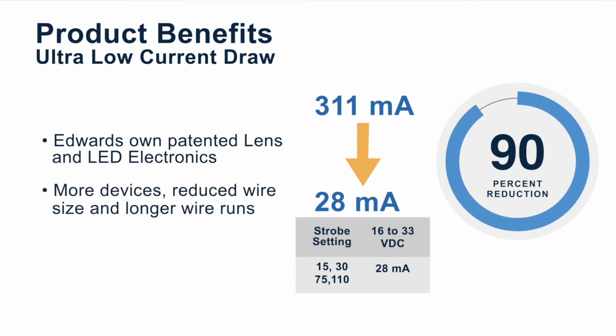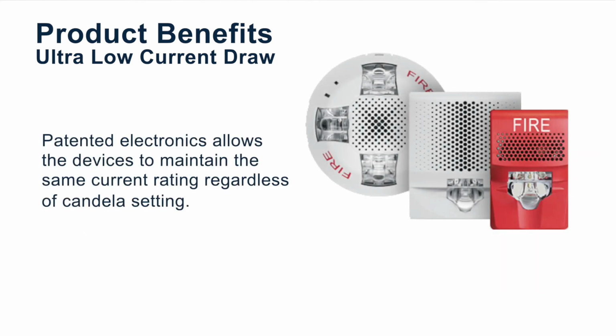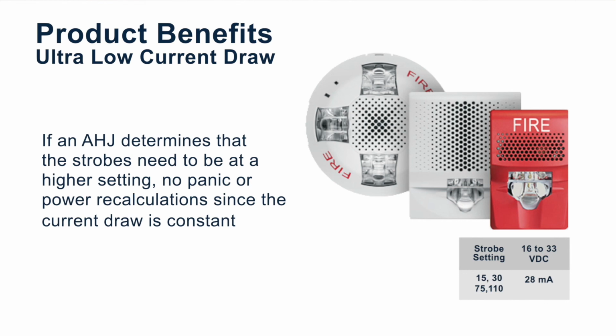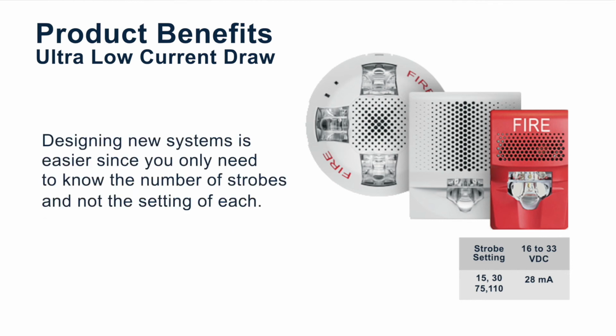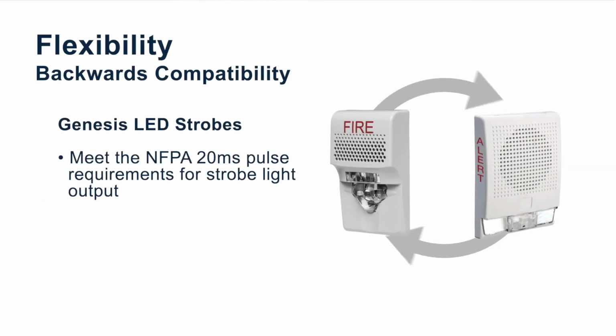This allows for the flexibility of more devices on a loop, reduced wire size and conduit, longer wire runs for more creative wiring solutions, and reduced booster power supplies. Part of the patented electronics allows the devices to maintain the same current rating regardless of candela setting. So if an AHJ determines the strobes need to be at a higher setting, there is no panic or power recalculations since the current draw is constant. Designing new systems becomes easier as well since you only need to know the number of strobes and not the setting of each. It is important to know that the new Genesis LED is backwards compatible with our legacy Genesis.